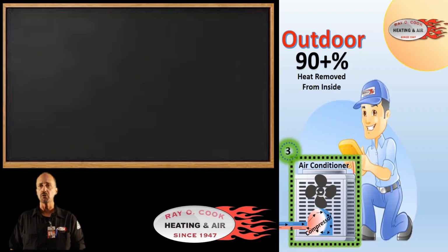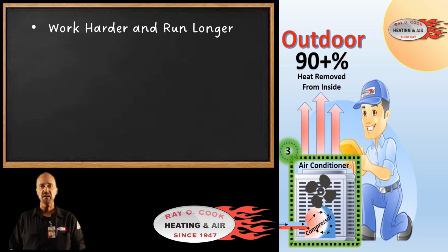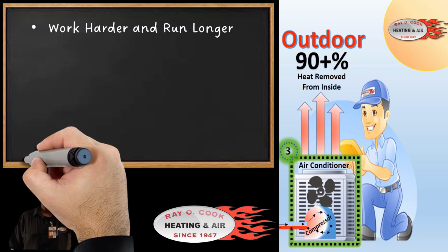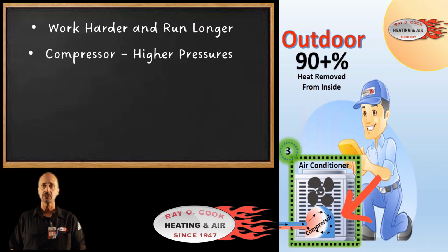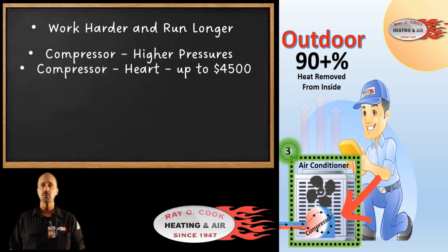A dirty outdoor coil will cause a few problems with the operation of your air conditioning system. Your AC unit will run longer and work harder to get rid of the heat that we have absorbed from inside your home. A dirty outdoor coil will also cause your compressor to work much harder under higher pressures. The compressor is the heart of the air conditioner and is one of those parts that is the most expensive to replace should it fail. Compressors can cost up to $4,500 to replace.